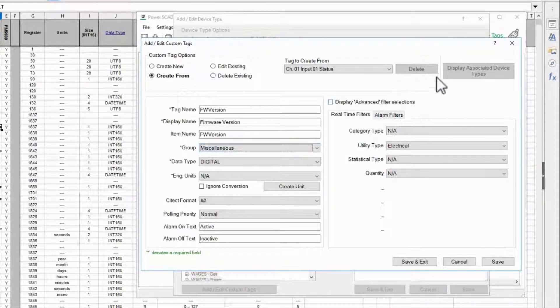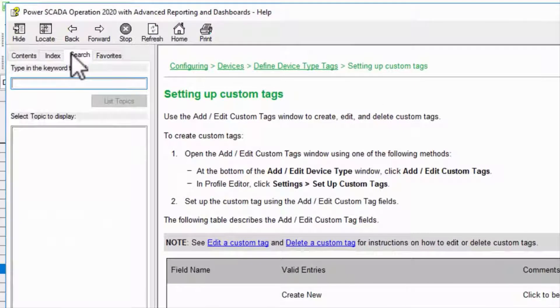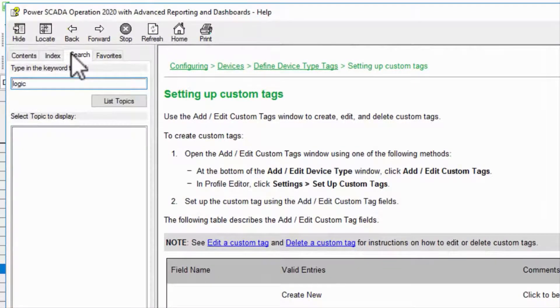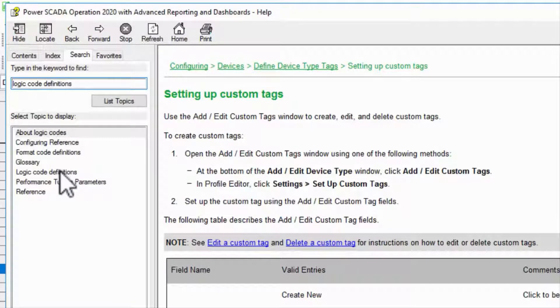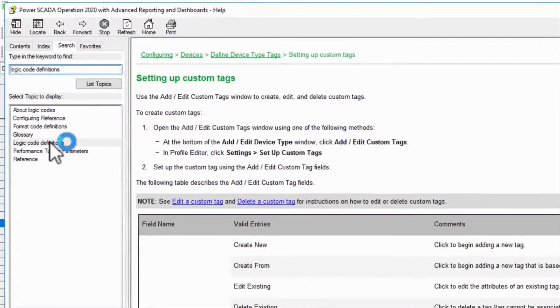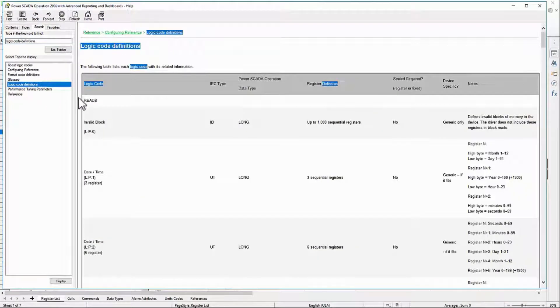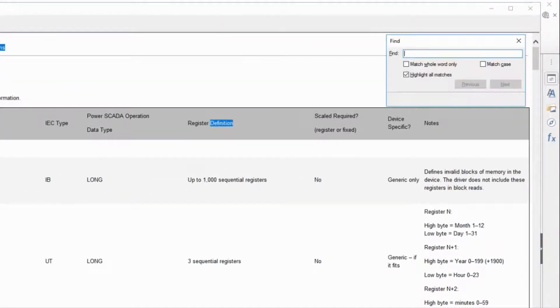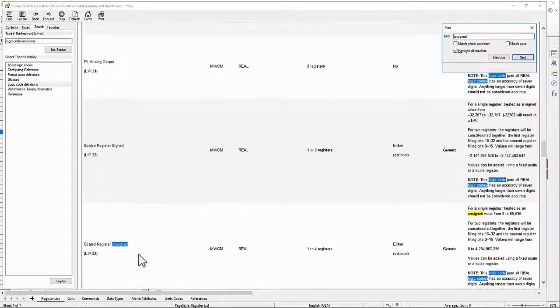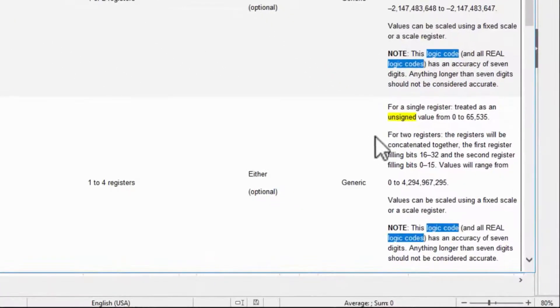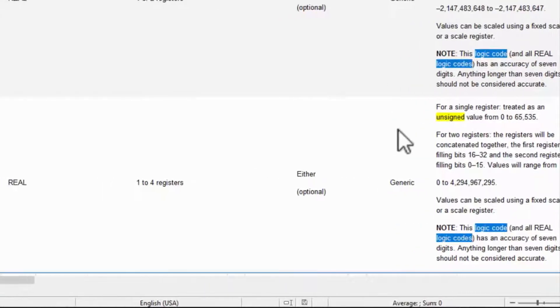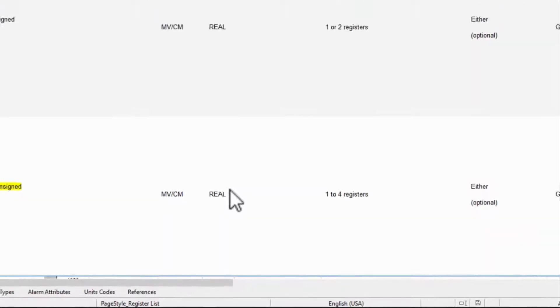Let me open up my help file to the page logic code definitions. If I search for unsigned here I'm taken straight to the scaled register unsigned. The description looks like the type of value I'm reading, and this is stored as a real tag so that's what I'll choose in profile editor.